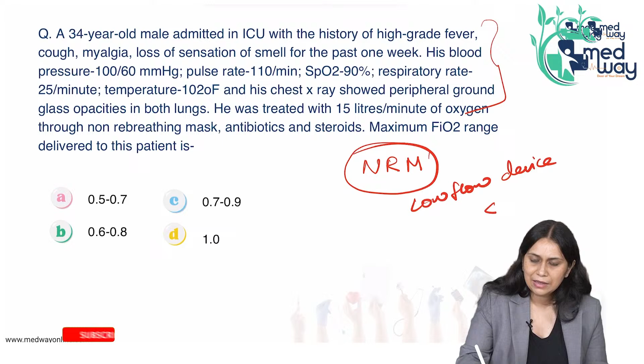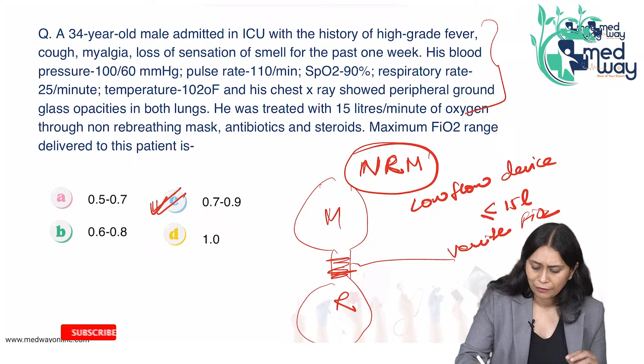So, what is the maximum FiO2 delivered by non-rebreathing mask? This device is a mask with a reservoir bag with a one-way valve between the mask and the reservoir bag. This gives a very high FiO2 of 0.7 to 0.9. So, remember, NRM, non-rebreathing mask, can give a very high FiO2. It can give maximum FiO2 among low flow devices.